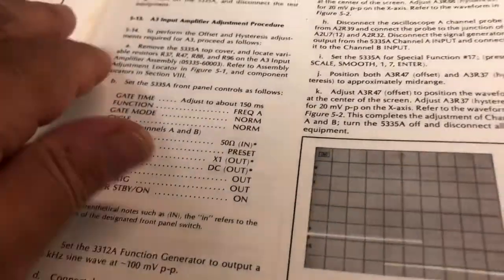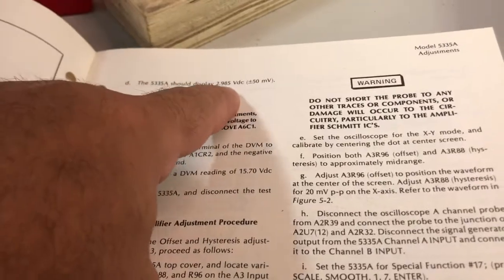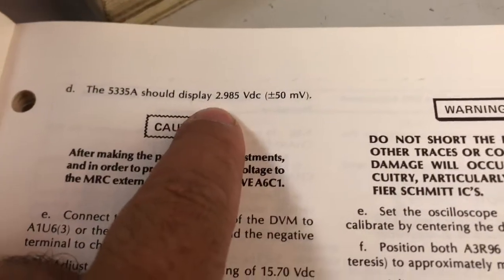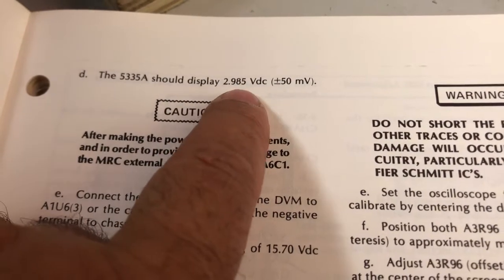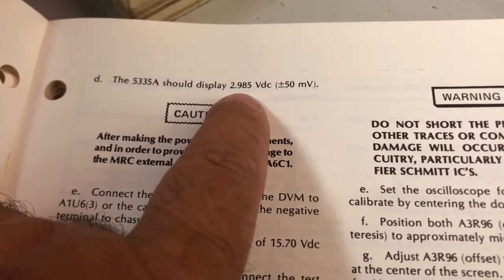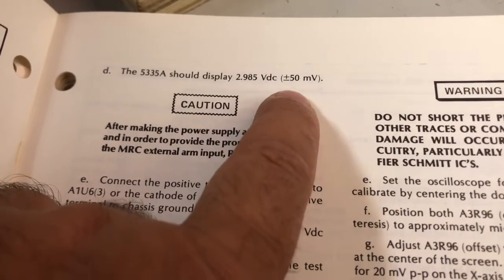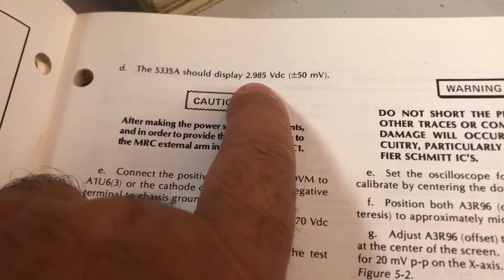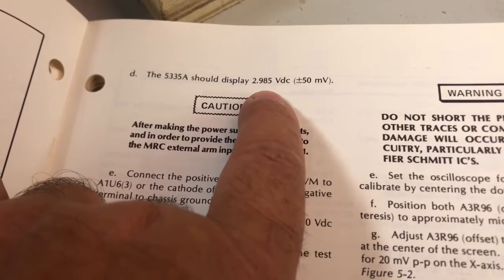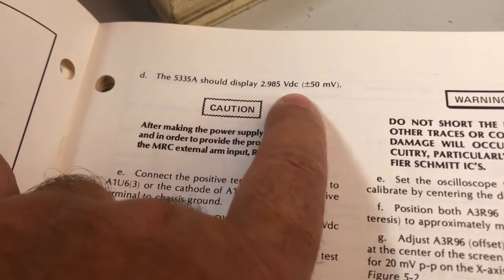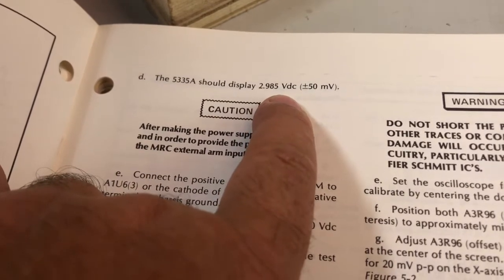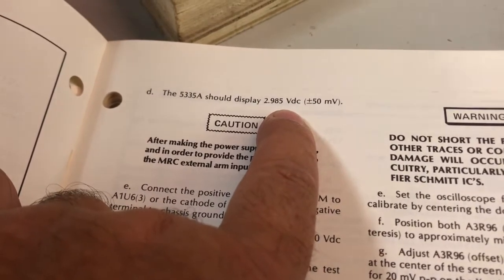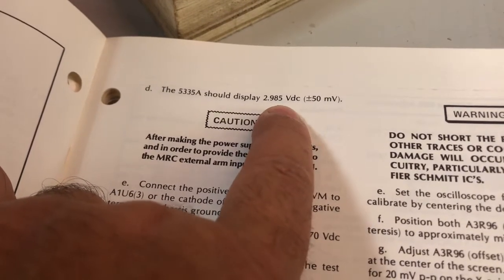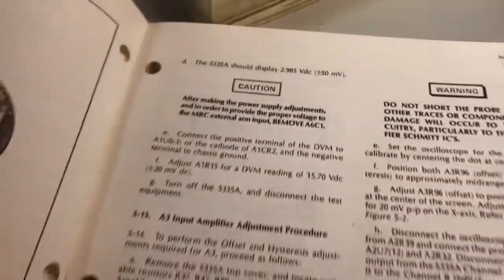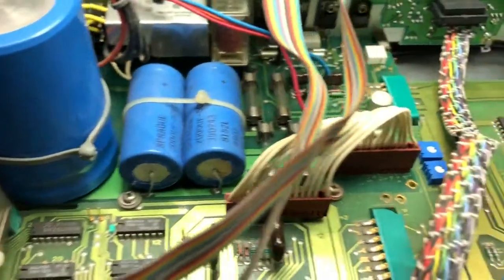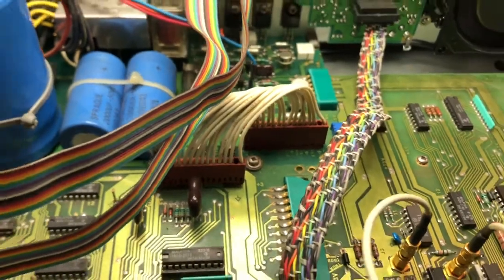since in the procedure here, put the instrument in a DVM mode that itself reads the DC voltage, and on the display we should see 2.985 plus or minus 50 millivolts, and indeed it's reading 2.92, so it's a bit low, but still I think... no, it's out, so it needs to be addressed. Perhaps the weak connection there is causing that.